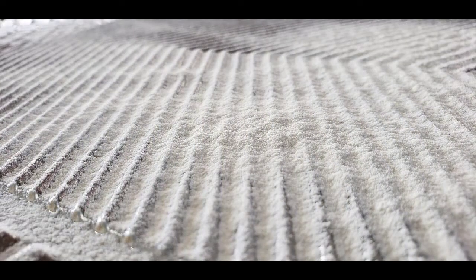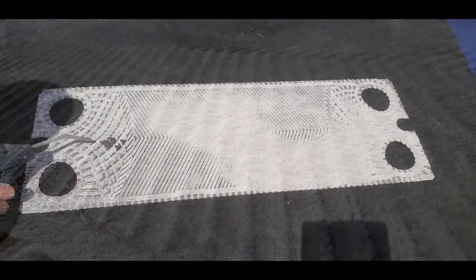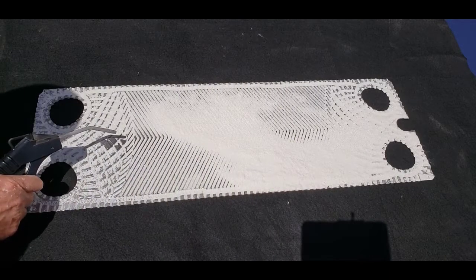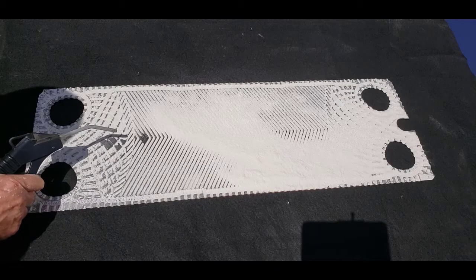So how can I reduce this risk? Well, if you keep operating the heat exchanger at lower capacity, the flow through the channel doesn't have enough sweeping effect to self-clean. That is the concept of shear stress: the higher the shear stress, the higher the sweeping effect.